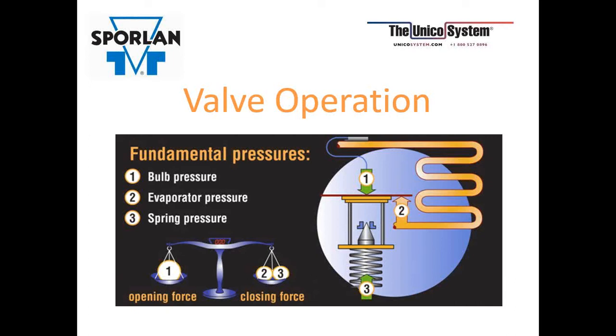And then there's superheat spring pressure. This is the amount of pressure that the spring has been set to maintain the desired superheat. It acts on the underside of the diaphragm as well, and works with the evaporator pressure to assist in closing the valve. In most cases, Unico supplies a non-adjustable TEV, so this spring pressure is factory set by Sporlan at the specifications given by Unico. And whether you're using an adjustable or non-adjustable version of the valve, the superheat spring pressure is a fixed pressure. Once it's adjusted, it stays there, it's fixed. The bulb pressure and the evaporator pressure change as the load changes, and that's how the valve either opens or closes.